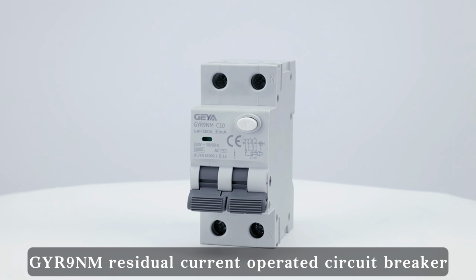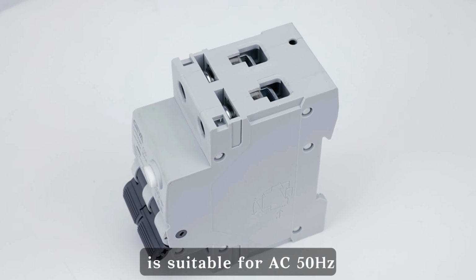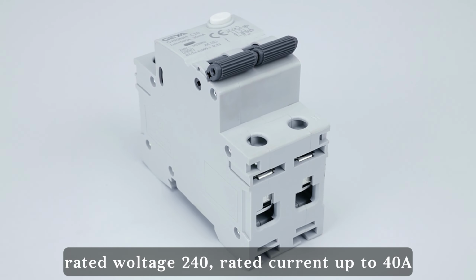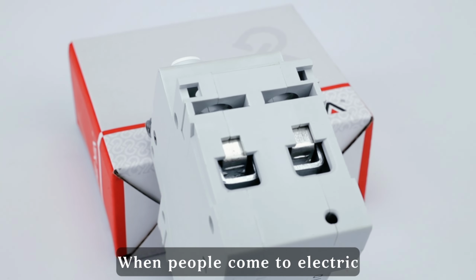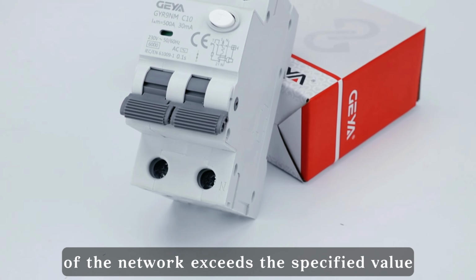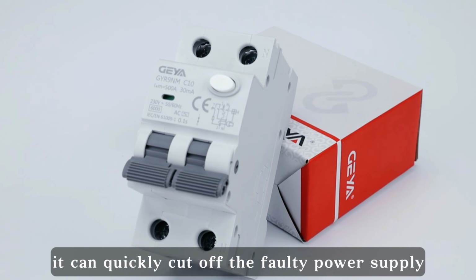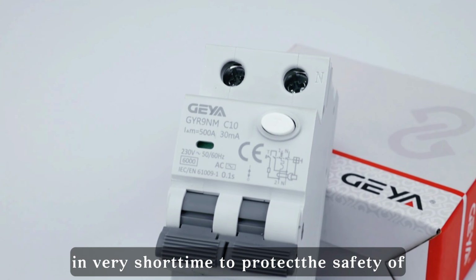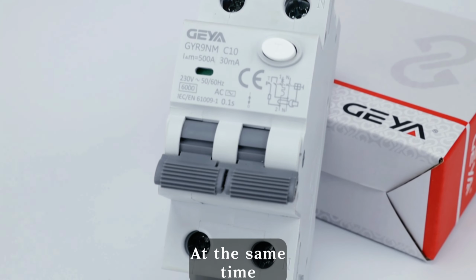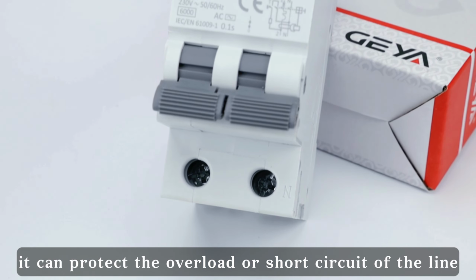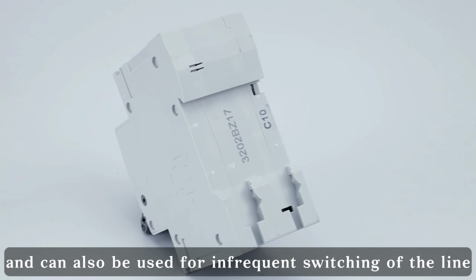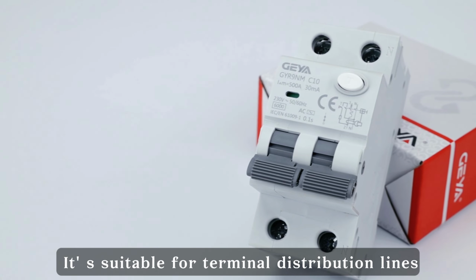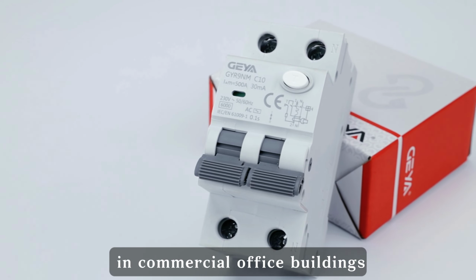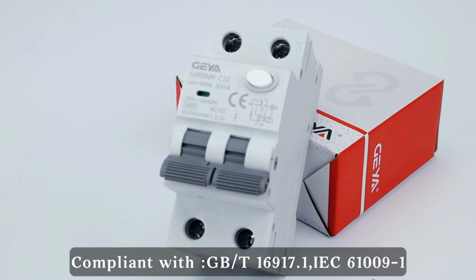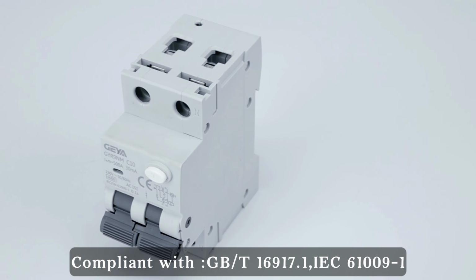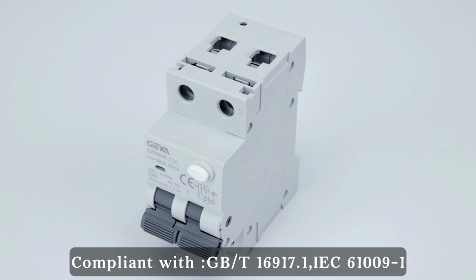The GYR9NM Residual Current Operated Circuit Breaker is suitable for AC 50 Hz, rated voltage 240V, rated current up to 40A. When people experience electric shock, or the leakage current of the network exceeds the specified value, it can quickly cut off the faulty power supply in a very short time to protect the safety of people and electrical equipment. At the same time, it can protect against overload or short circuit of the line, and can also be used for infrequent switching of the line. It is suitable for terminal distribution lines in commercial office buildings, residential buildings, and general industrial use. It complies with GB/T 16917.1 and IEC 61009-1.